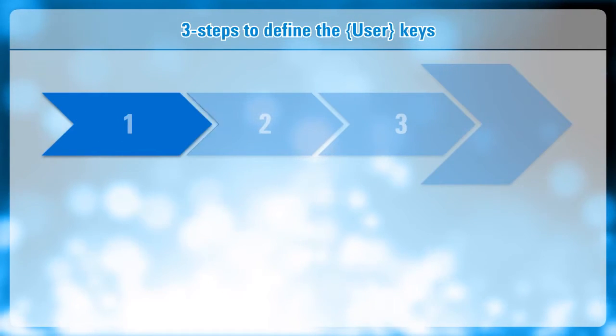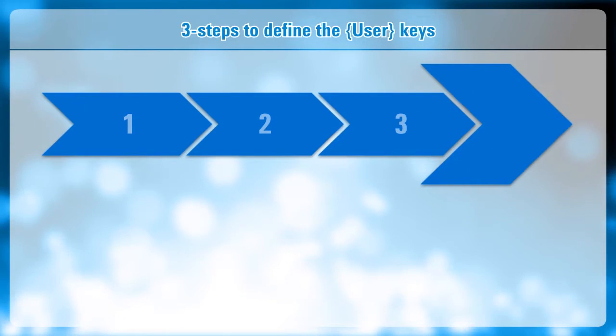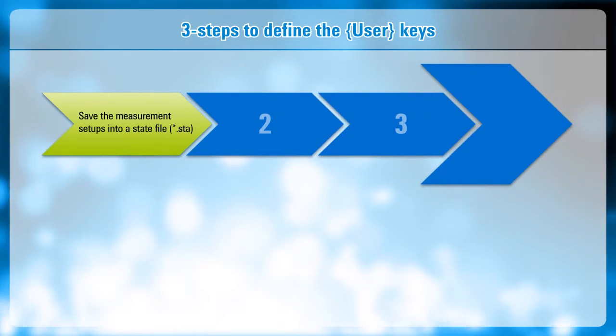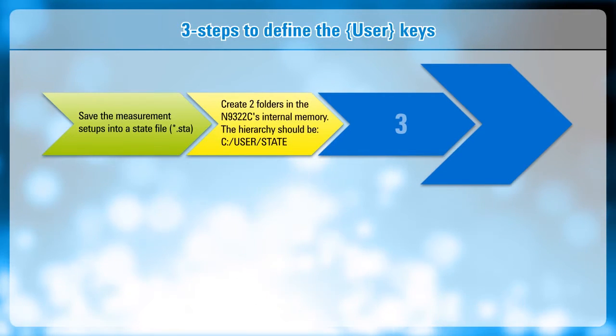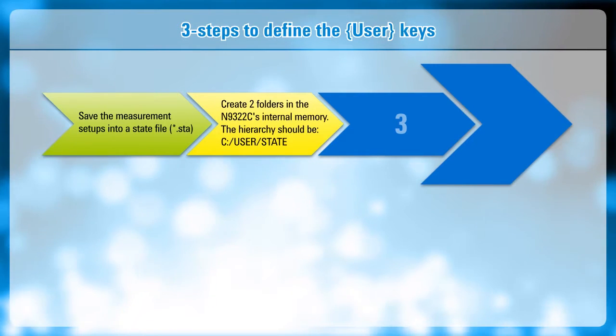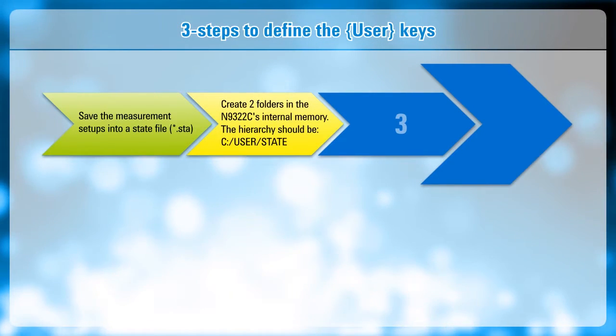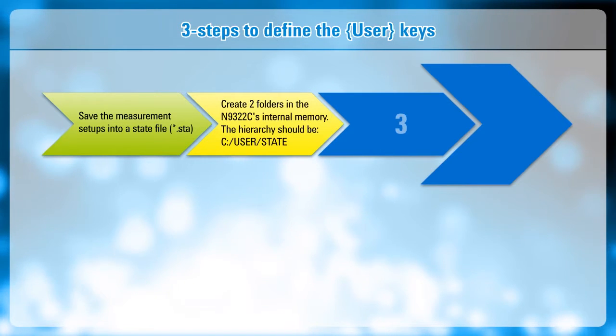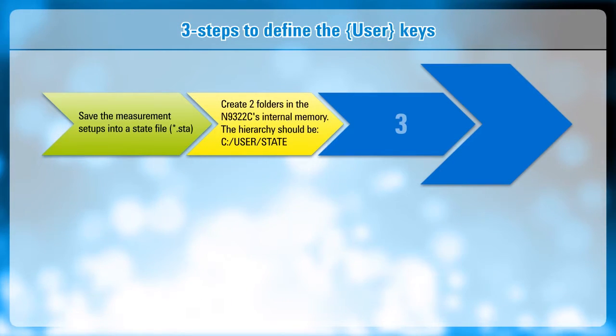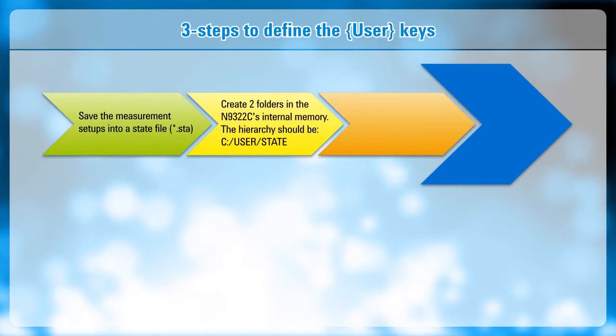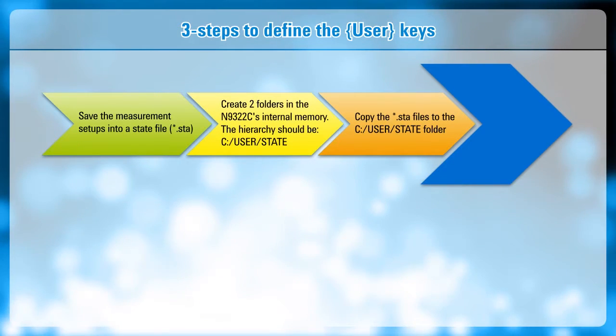It takes just three simple steps to establish the functionality of your user key. First, you need to save the measurement setups into a state file. Then, you need to create two folders in the N9322C's internal memory. The hierarchy should be C colon backslash user backslash state. For the final step, copy the state files to the state folder you just created.